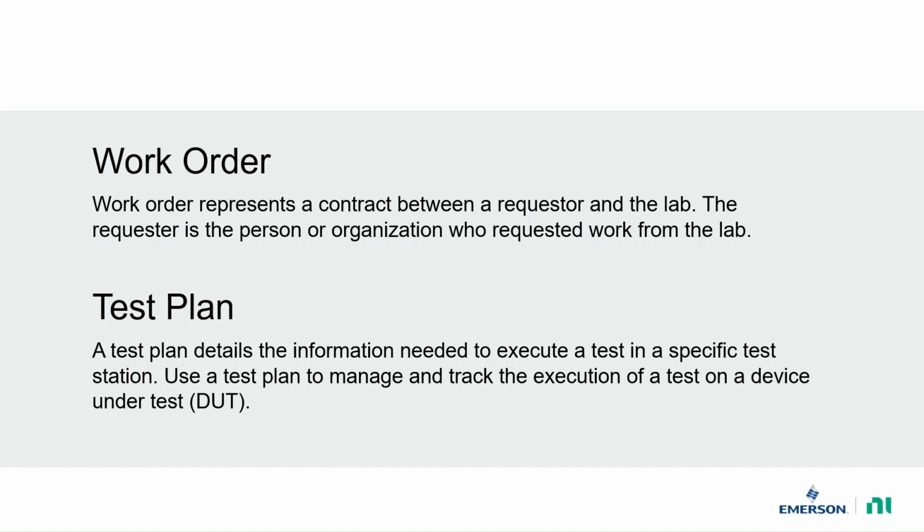A test plan details the information needed to execute a test in a test station. The test plan includes details about the test program, test parameters, the DUT that needs to be tested, etc. A work order can have multiple test plans under them, one each for the different tests that have to be carried out on the device.